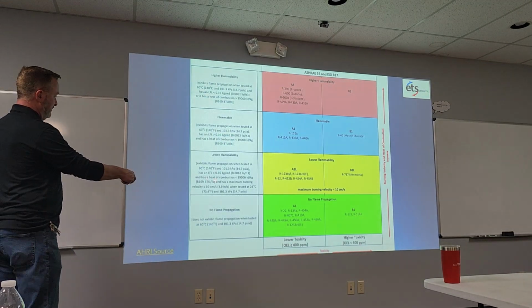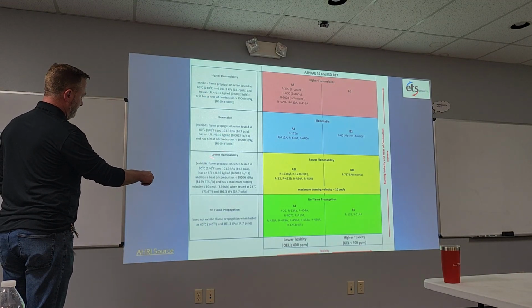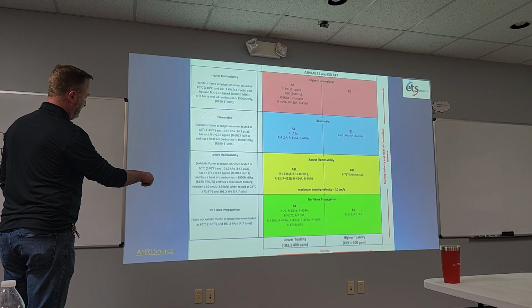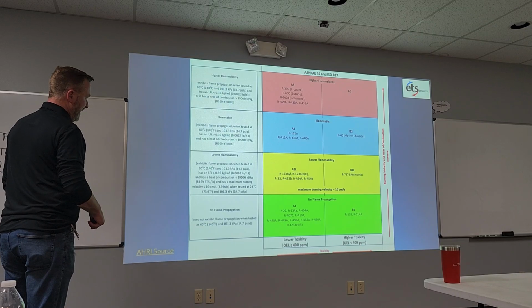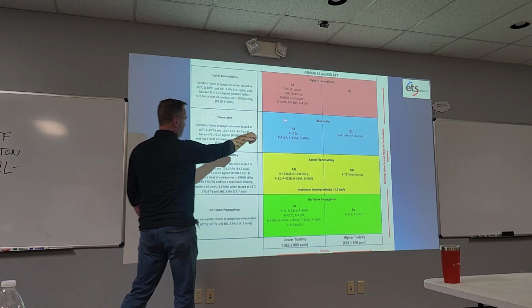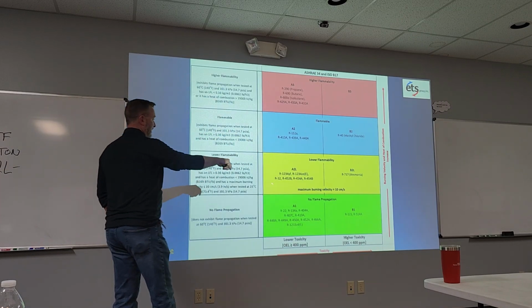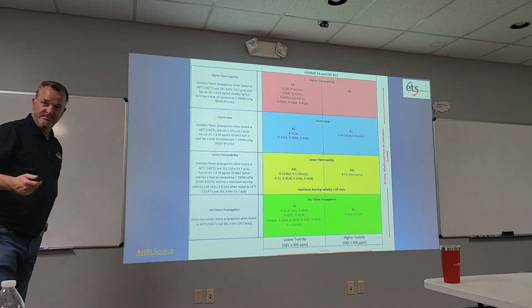Then with A2Ls, the mildly flammable ones we're going to be dealing with, the LFL is lower, with a heat of combustion around 19000 and a certain maximum burning velocity. So A2s are considered flammable, while A2Ls are considered lower flammable.